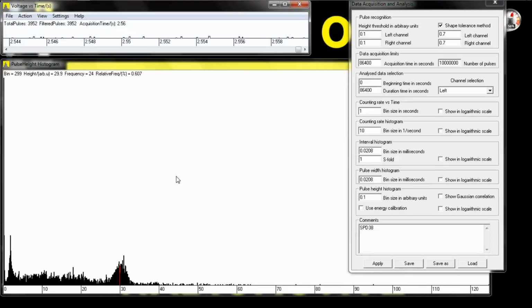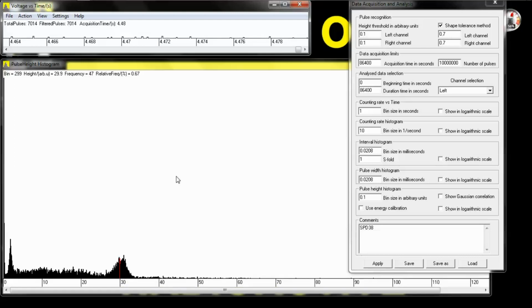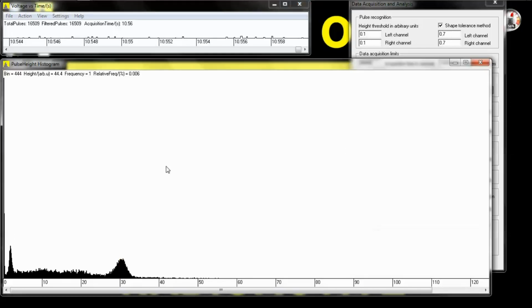See, now it looks a little better. This is what it looks like when I change it to 0.1. Less pulses are being accepted. A lot less pulses are being accepted because this thing is being way more discriminative in the sound that it accepts. You'll notice that the primary peaks still show up. And depending on what kind of analysis you're doing, it could be more preferable to have this sort of setup.